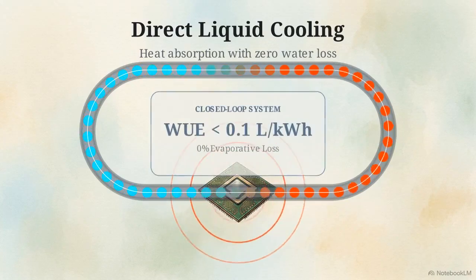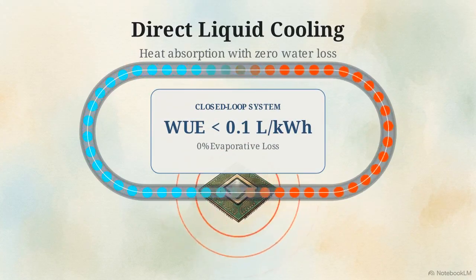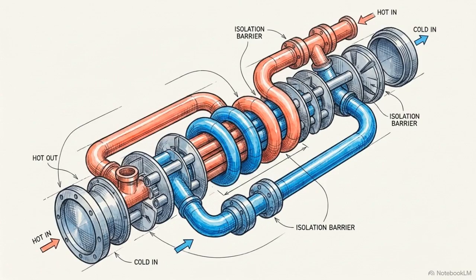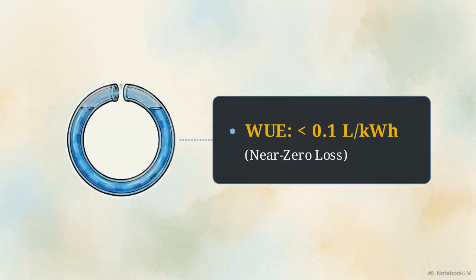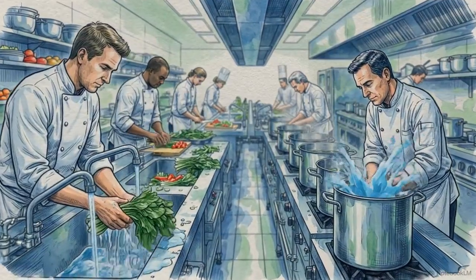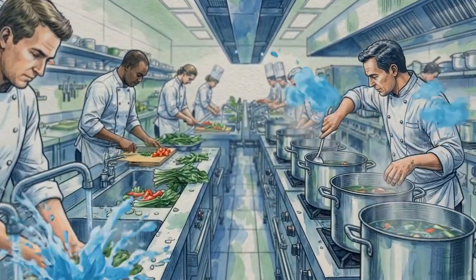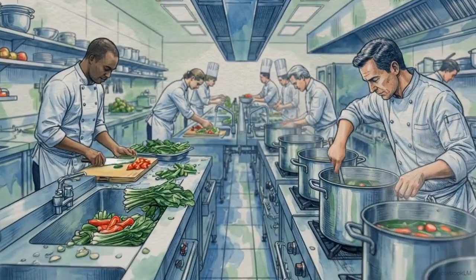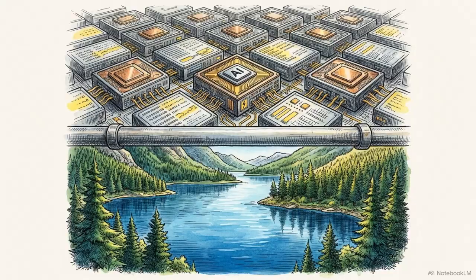The critical distinction is that this liquid remains entirely trapped within a closed loop. The absorbed heat is transferred out via secondary mechanical systems. The primary fluid is never exposed to the outside atmosphere. By sealing the architecture, operational water loss plummets. The water usage effectiveness drops to less than 0.1 liters per kilowatt-hour. To put that near-zero loss into perspective, a 30-megawatt closed-loop facility uses no more operational water annually than a standard commercial restaurant. Shifting to a closed-loop architecture mechanically decouples the scaling of AI networks from local water depletion.